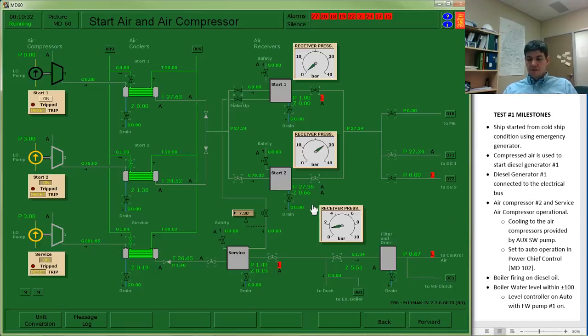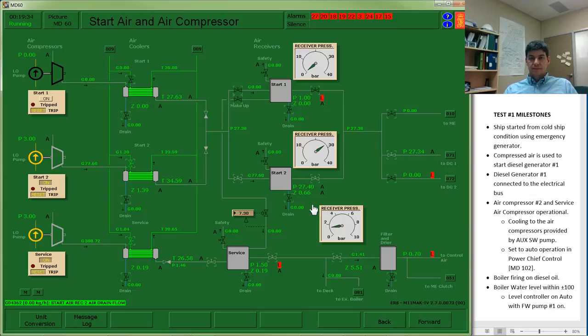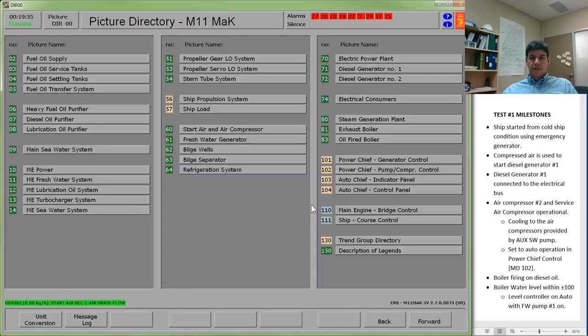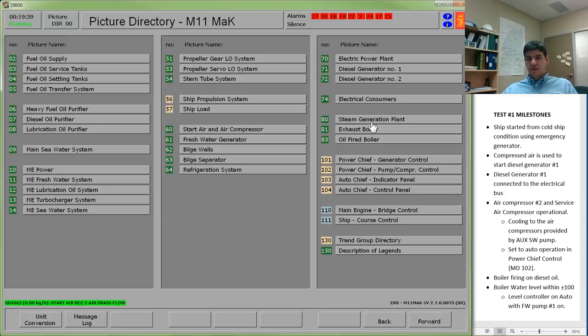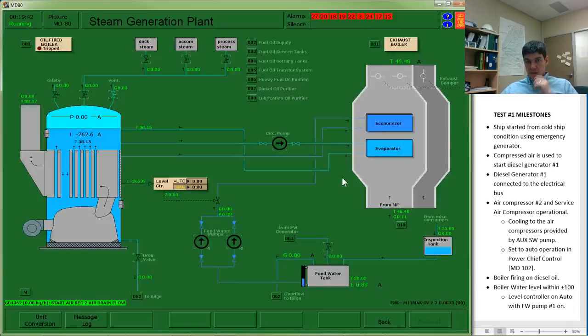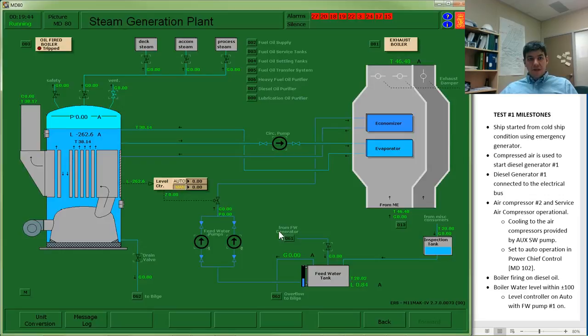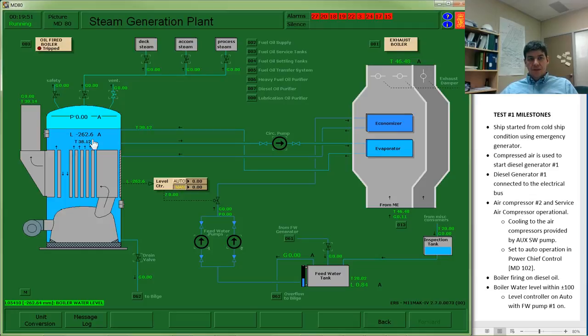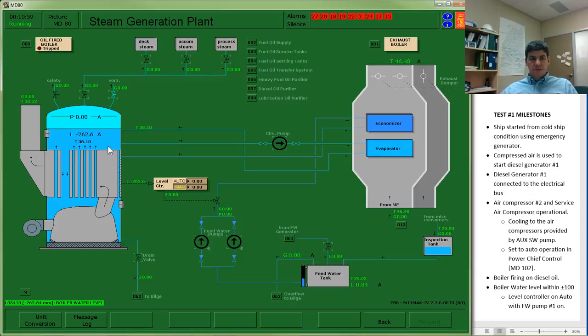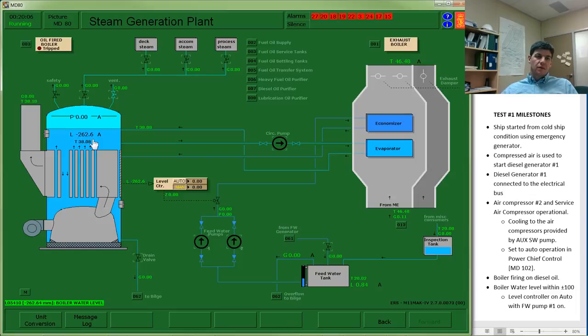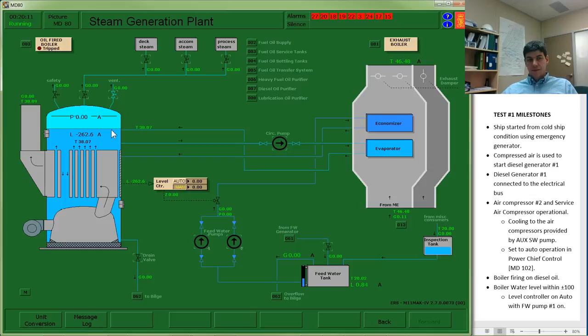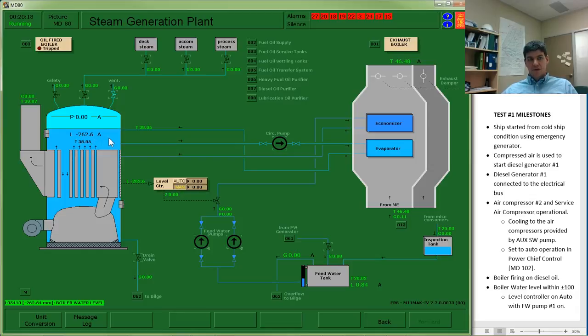So the boiler is two pages. Page 80 and 83. First thing that we want to do with our boiler is make sure that we have water in it. So the water is shown here by the level. Right now it's negative 262, which means it is 262 millimeters below my normal operating point. If it was positive, it would mean it was above. And what that means is that my target for water in the boiler is going to be zero. Right now I'm low. The low cutoff for the boiler happens at negative 300. So I'm pretty close to that level. So I want to add in some water into the boiler.